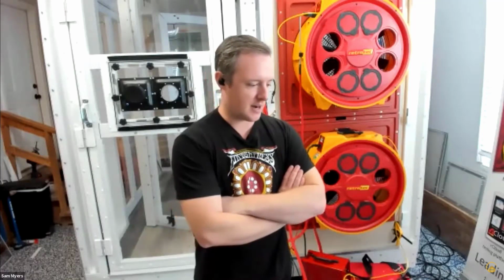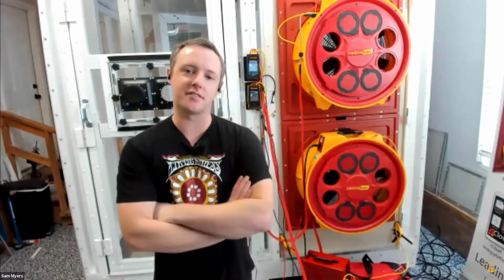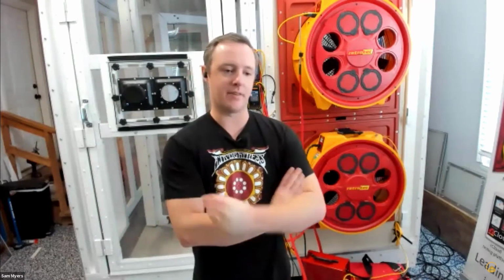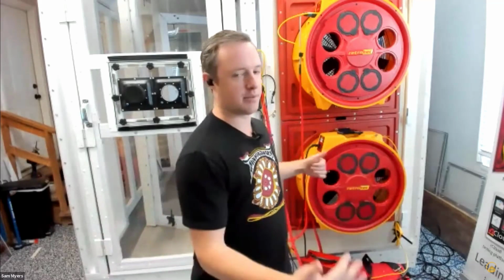I know you mentioned briefly at the beginning how you do smoke tests sometimes - is there anything different about this setup that you would do if you were going to do a smoke test? Yeah, so when I do a smoke test, I always like to set it up to pressurize the building, especially if I'm within the building envelope itself. That way I want to make sure all other mechanicals are turned off - exhaust fans, HVAC system - so the only air moving is the pressure I'm generating from my blower doors.